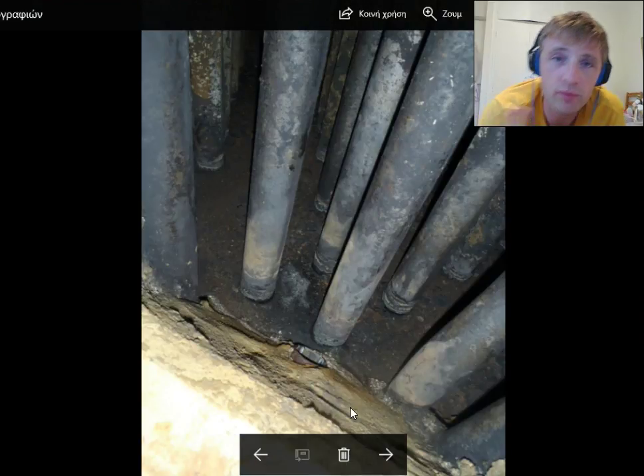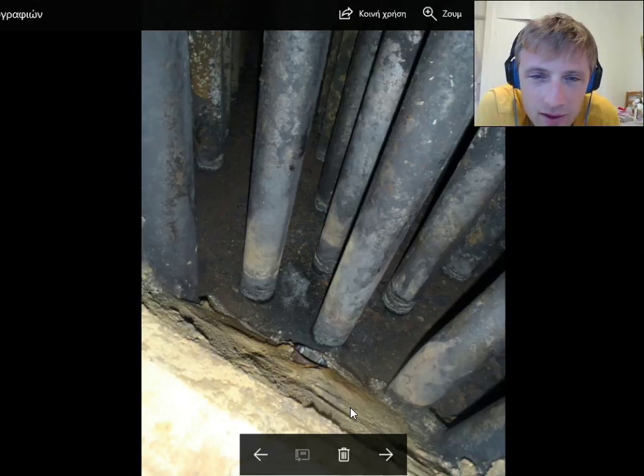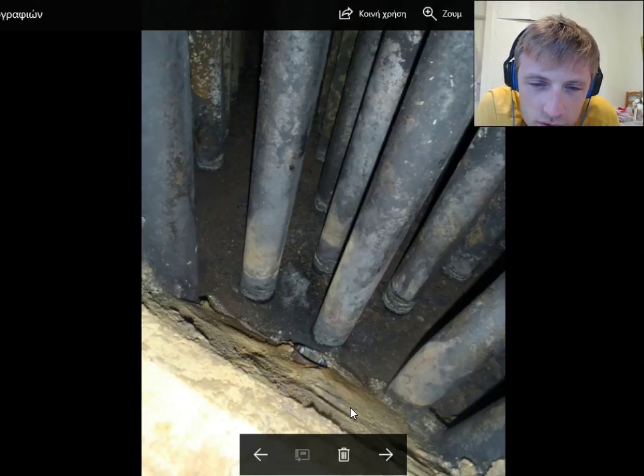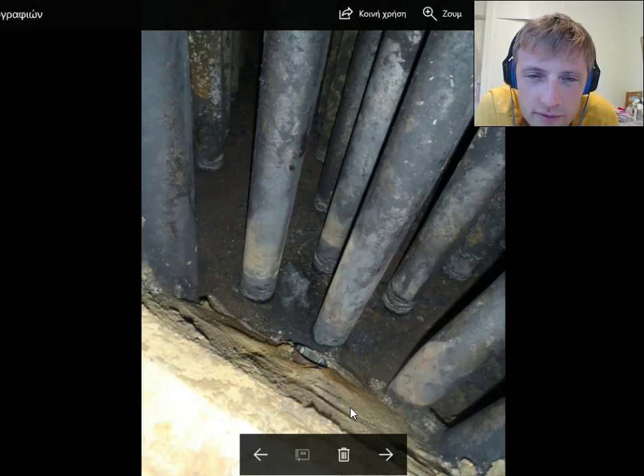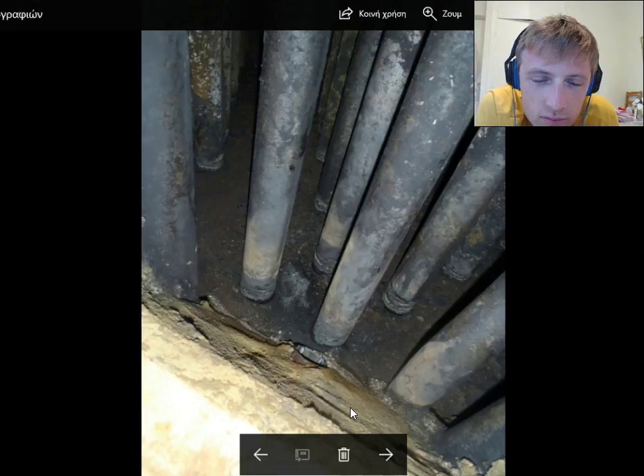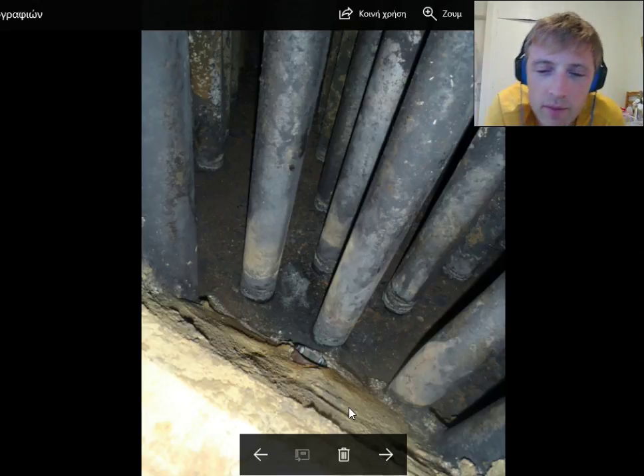When you make washing with high pressure machine, you need to open one drain which goes to the settling tank. This drain is at the back of the boiler. You need to monitor so the drain is working and free to not block, and water coming down.